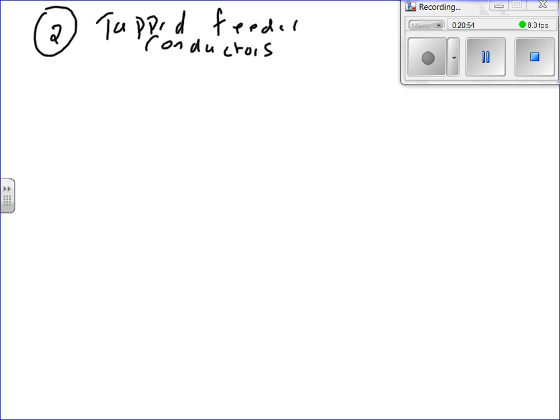Okay, so here's the rule. I want to remind you guys, it's a 10-foot tap, not 20, Chad. Because it's a 10-foot tap, the tap conductor cannot be less than 1/10 of the overcurrent protection device.